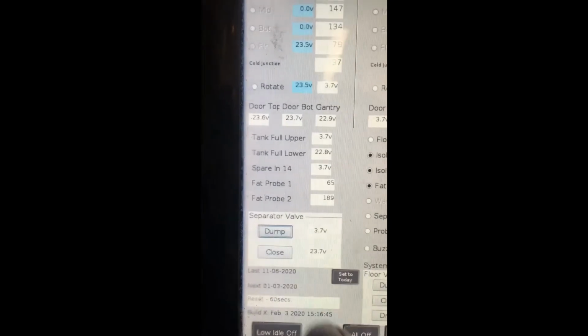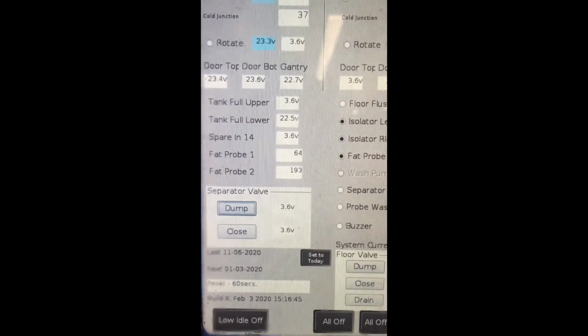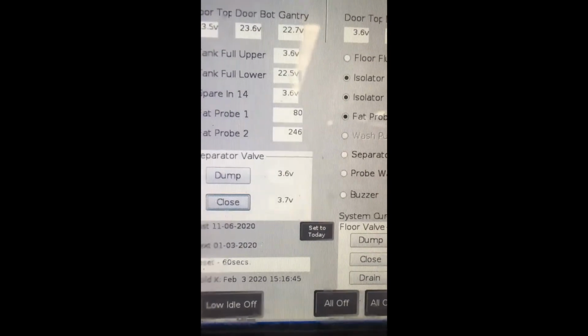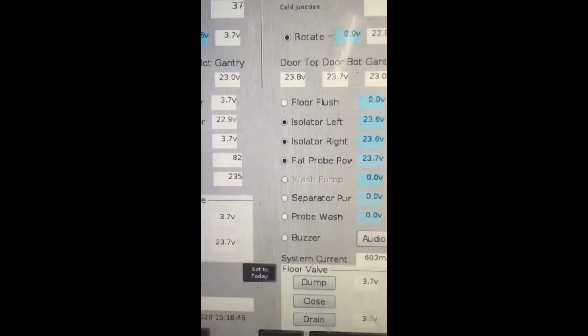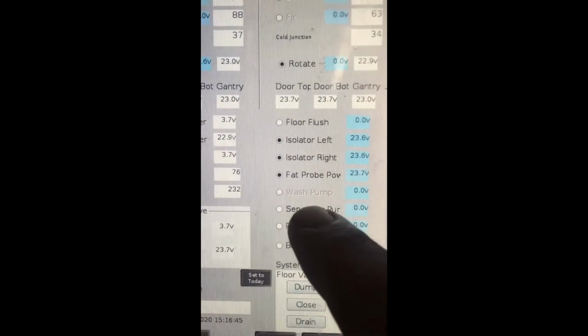Press on dump. You should hear the motor actuated valve turn. And as we come down and look into the fat separator, we should see the fluid levels drop. Drain approximately half the fluid from the tank, then come back up and push close. We are now going to test the separator pump. To turn the pump on, tap on separator pump.